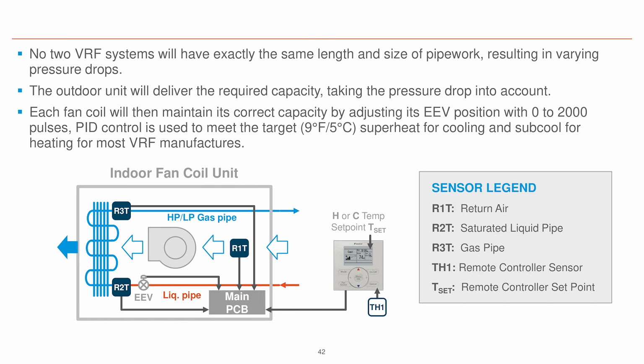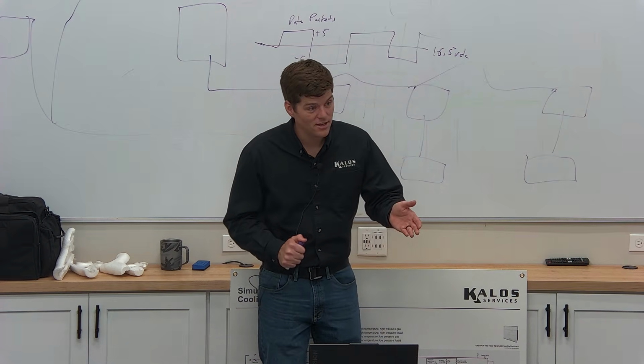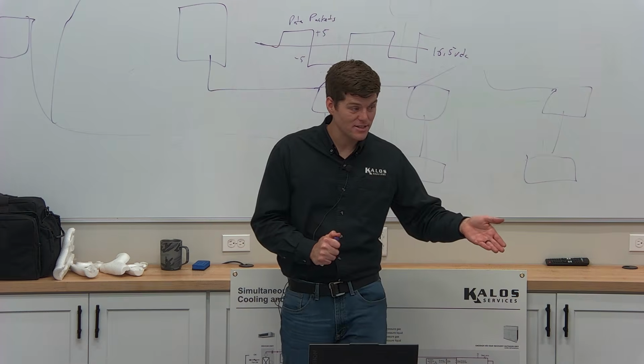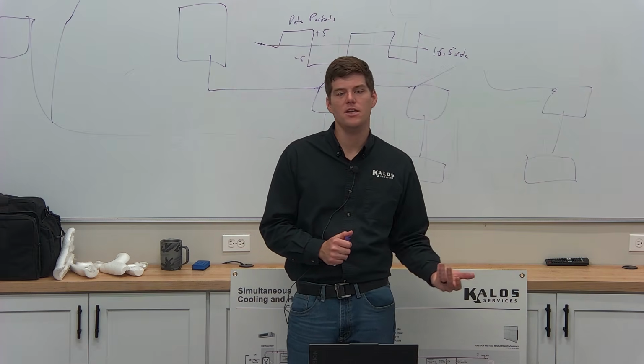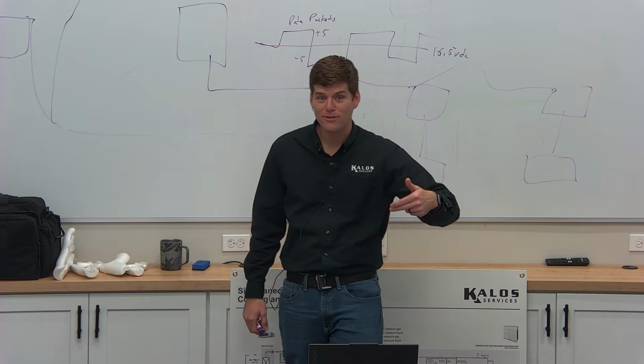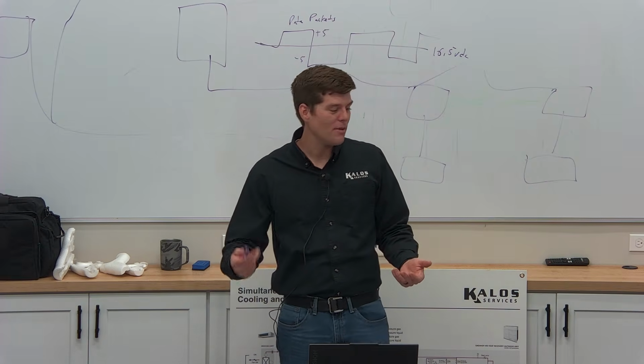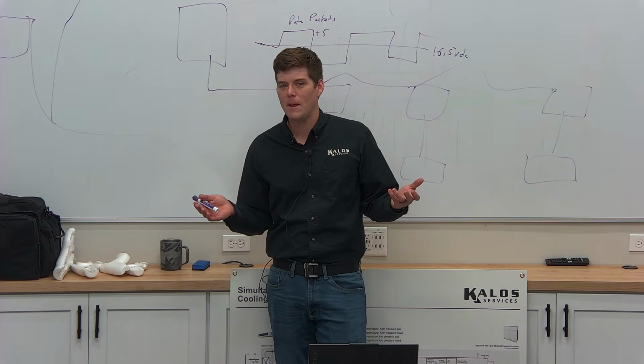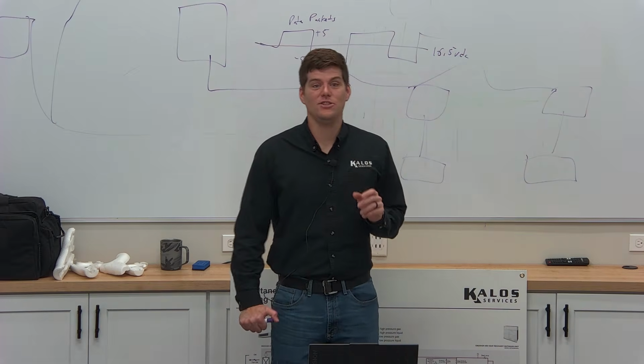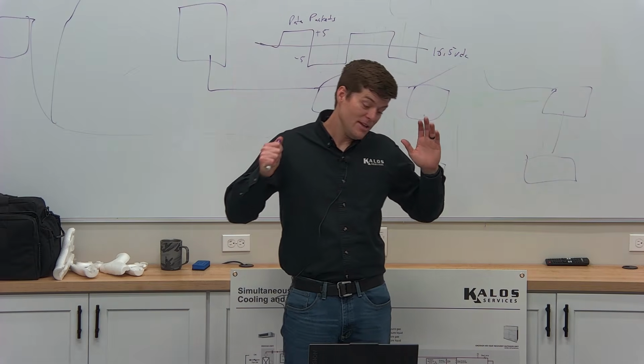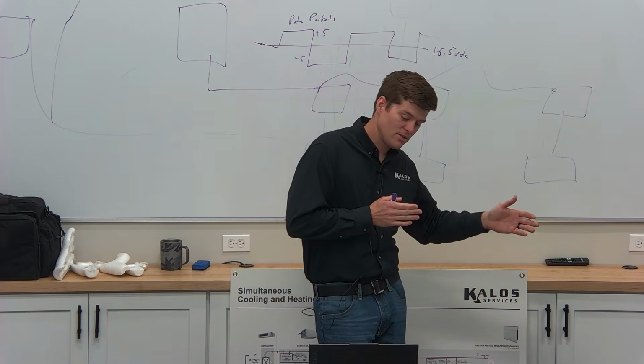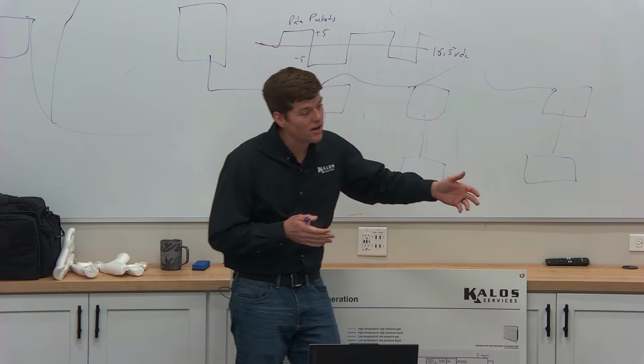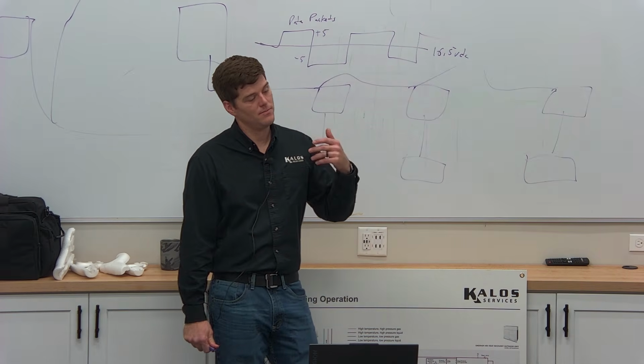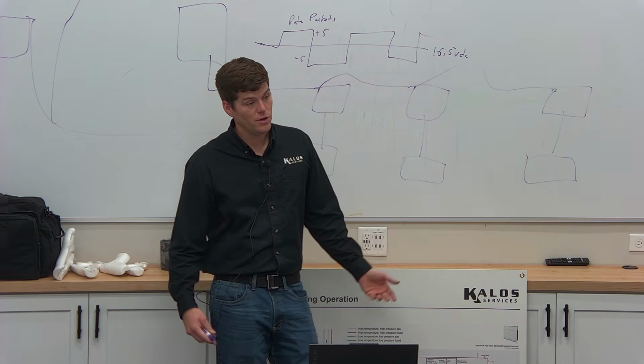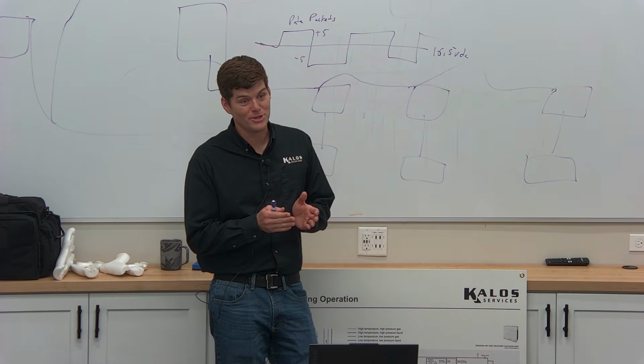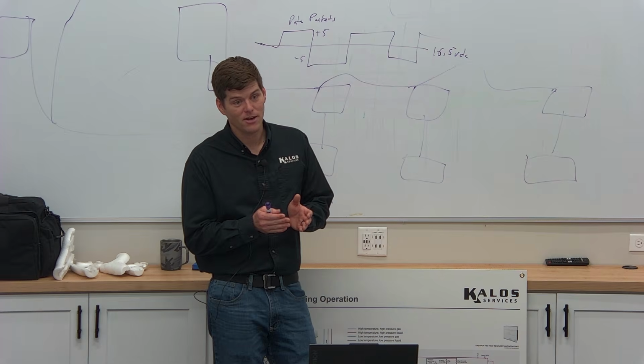The importance behind that is because if your temperature sensor is faulty and it's misreading on its resistance because the sensor is old or it was overheated, someone took a torch to it and cut off the flare fittings because they're in a hurry. And you know what? I've been doing this for 30 years. You don't have to tell me otherwise. So if the temperature sensors on these units are 5 degrees off, if they're 20 degrees off, if they're anywhere close to that, it can become an issue. The unit thinks that it has a 20-degree superheat when actually it has a 0-degree superheat. What's happening now?